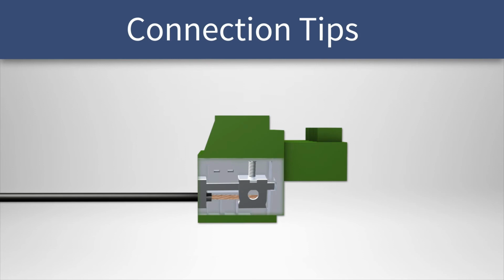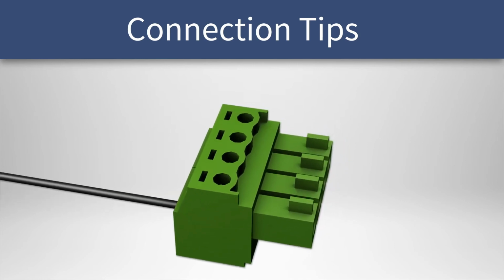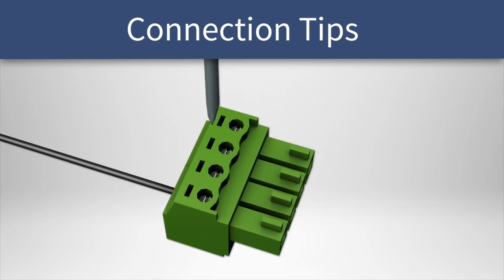That being said, exposing too much bare wire should be avoided, as this could pose the risk of bare wires touching each other outside of the terminal block, which could create a short and lead to incorrect readings. Use the screws in the terminal block to fasten the wires in each port securely, while also being careful not to over-tighten them.